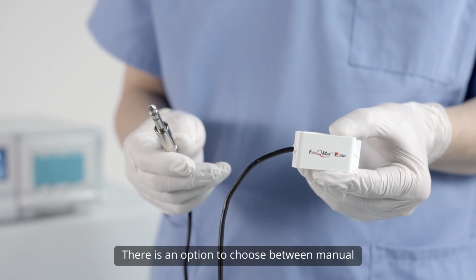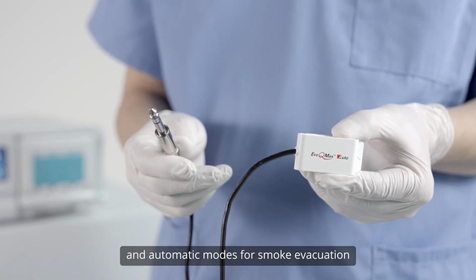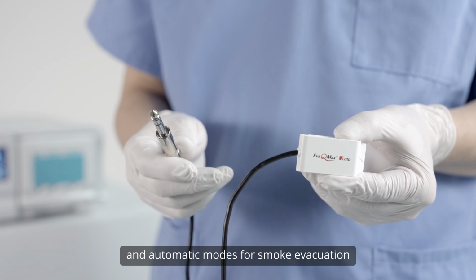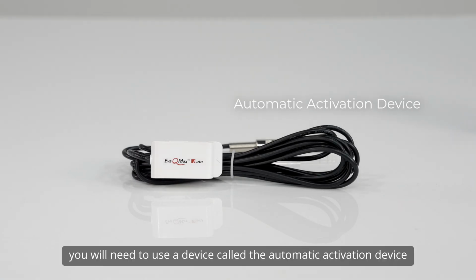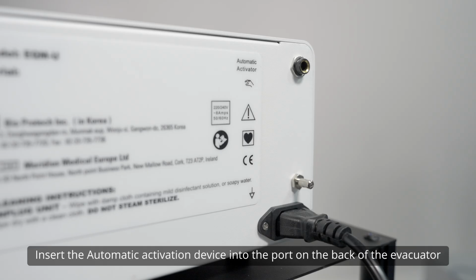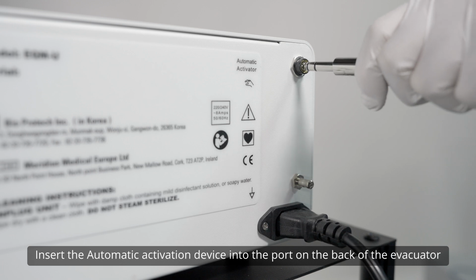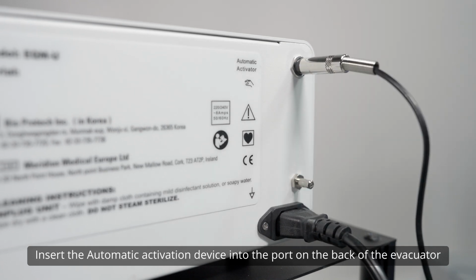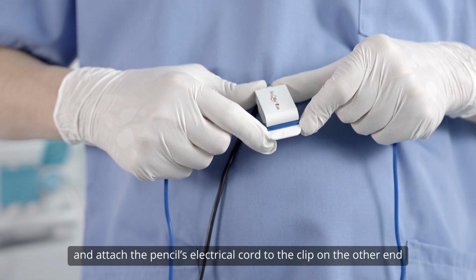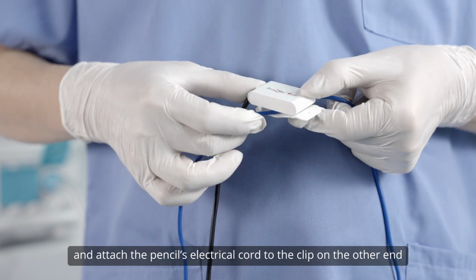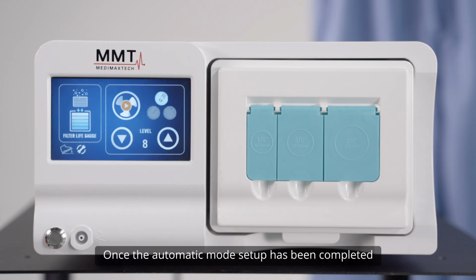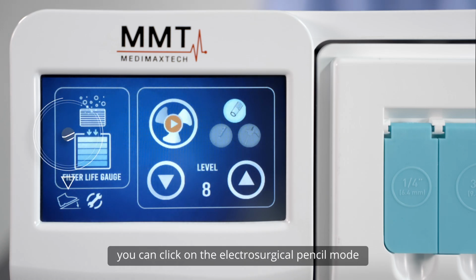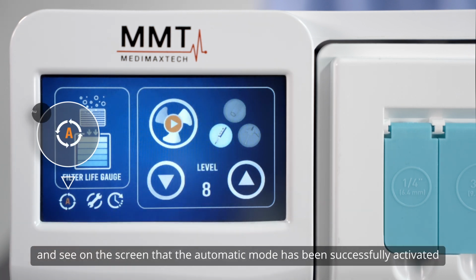There is an option to choose between manual and automatic modes for smoke evacuation. In the case of automatic mode, you will need to use a device called the automatic activation device. Insert the automatic activation device into the port on the back of the evacuator and attach the pencil's electrical cord to the clip on the other end. Once the automatic mode setup has been completed, you can click on the electrosurgical pencil mode and see on the screen that the automatic mode has been successfully activated.